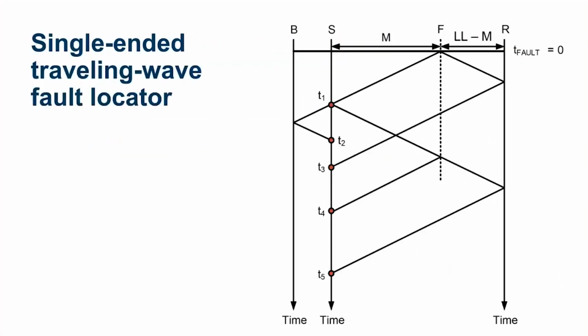So let's say you don't have access to a high-speed fiber connection between the relays, or maybe the relay fiber got cut. Maybe it was because of the fault. We can revert to a single-ended traveling wave fault locator. So if we just look at terminal S here, a wave is going to be launched from the fault point to terminal S at this point T1. Now at this point, when it reaches this terminal, we're going to see some of the wave pass through to the remote bus, and some of it is going to reflect.